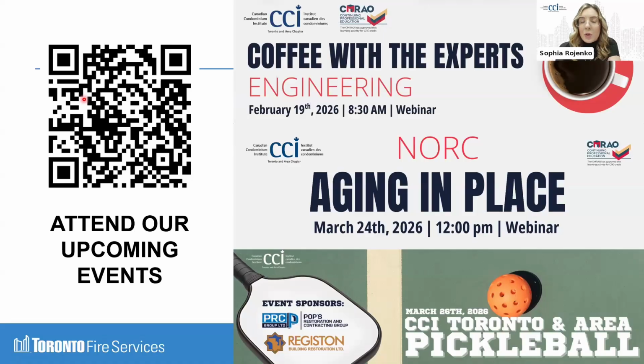Okay. Is there a list of certified technicians that can be hired for consultations? What certifications are being vetted by the group of experts, and what are the methods of verification being used? So verification of building systems is done, first of all, at the commissioning stage on their building permit. What the fire code requires on an ongoing basis, the big one is CFAA, Canadian Fire Alarm Association, for anybody touching your fire alarm system and doing your annuals. So CFAA certification is mandatory. And for your CAN/ULC-S1001, doing the verification and doing annual fire alarm inspection, testing, and maintenance with the CFAA certification will cover 90% of it. But CFAA certification for anything fire alarm related, that's the big one.